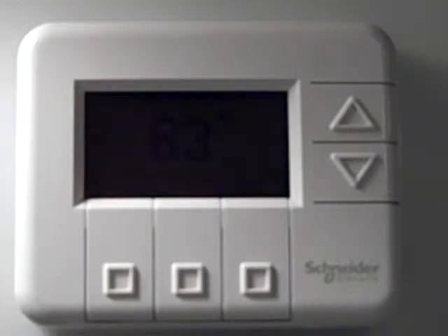One of the things that we need to make sure of is that any thermostat that we have needs to get put on the proper network. Thermostats are assigned by floor categories. If there's 4 floors typically, we might have them on first and second floor associated together, and then on the third and fourth, or by sections of the building. It's important to make sure that when you're putting a thermostat on the network, either for the first time or in a replacement situation, that you do put it on the right network.